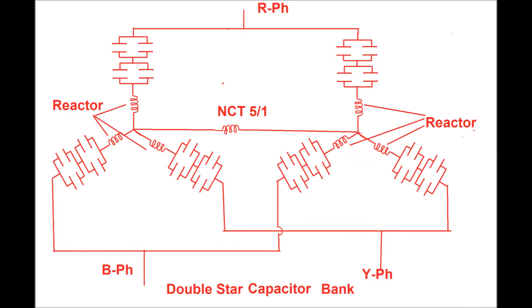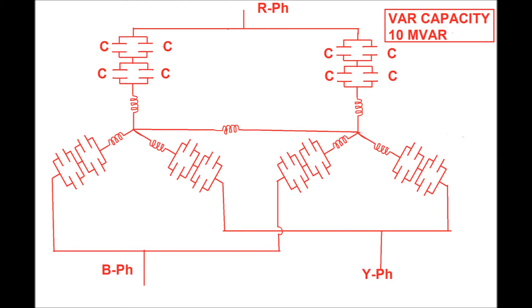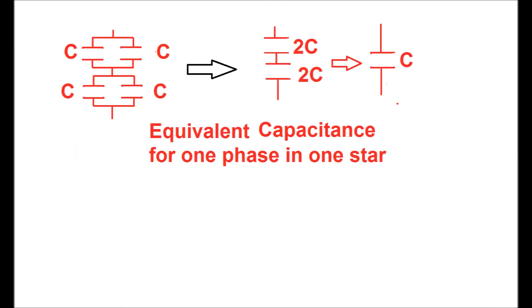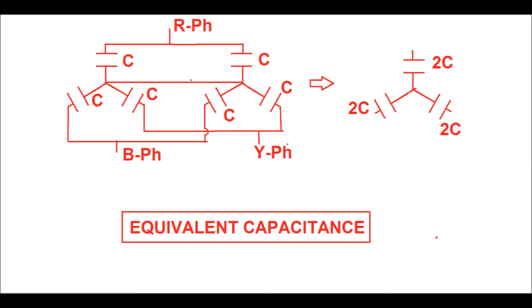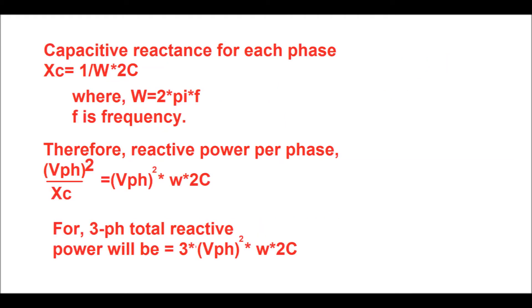Now we will calculate the capacitance unit value for a 10 MVAR capacitor bank. First, we convert the parallel combination capacitor units to a single unit. If C is the capacitance of each unit, then for each parallel combination the value becomes 2C. The 2C and 2C in series gives C. Therefore, the equivalent capacitance for one phase for one star is C. The equivalent capacitance for each phase for the double star is 2C.